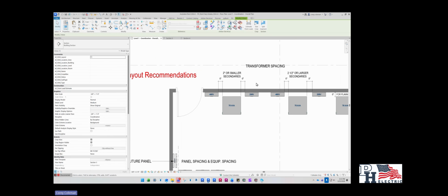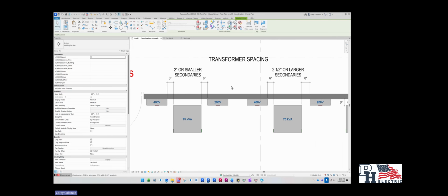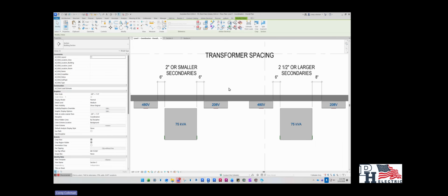When we're working with transformers, there's a couple of different things you want to maintain. When you're dealing with 2-inch or smaller secondaries, you want to have your spacing of 6 inches between your primary and your transformer, as well as your secondary and your transformer. This allows you to work with the fittings as well as keep the copper length down. It also provides a nice, clean, symmetrical look.